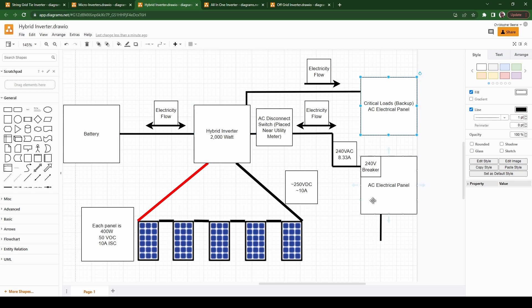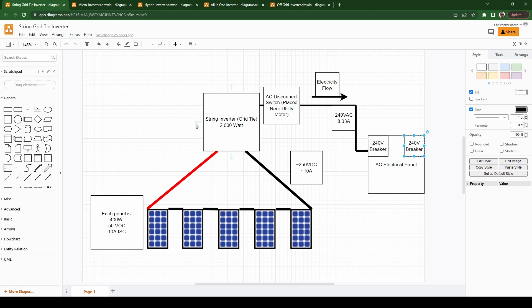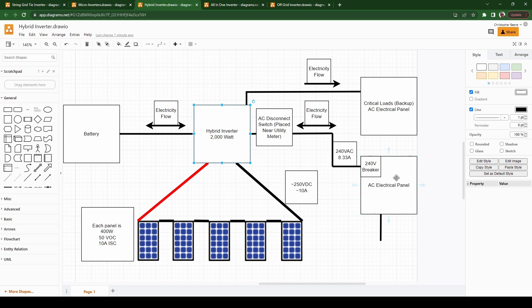You can have loads, a panel that can be run off of just battery and panels as opposed to requiring the grid to be on. When you're in a pure grid tie scenario your electricity flowing only one direction. As soon as this AC disconnect switch is tripped or the breaker is turned off or there is no grid anymore, this grid tie inverter will shut down. That's according to UL 1741, an anti-islanding feature, and that's safety for those that are working on the grid.